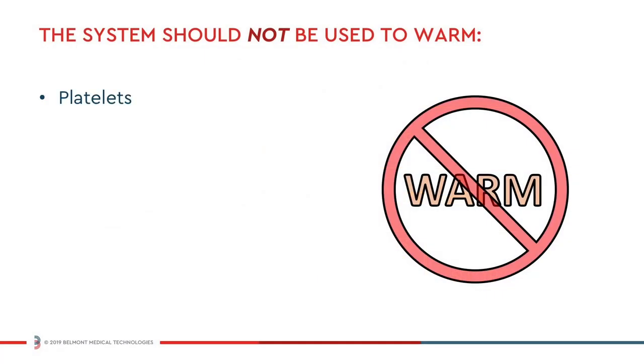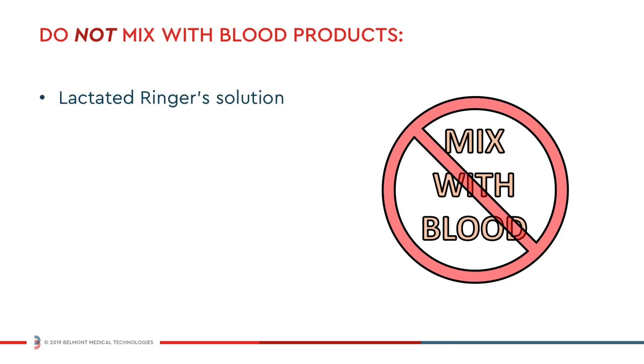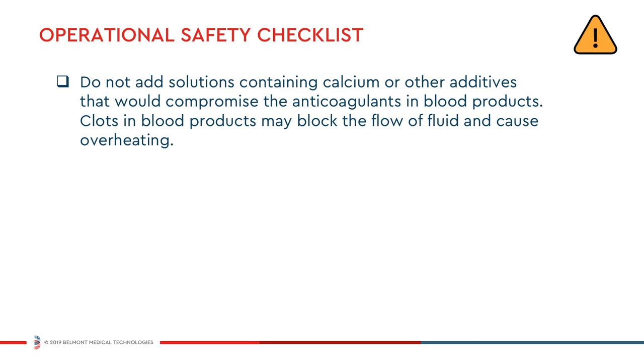The system should not be used to warm platelets, cryoprecipitates, or granulocyte suspensions. Lactated ringer solution, dextrose in water, and hypotonic sodium chloride solutions should not be added to blood components. Do not add solutions containing calcium or other additives that would compromise the anticoagulants in blood. Clots in the blood products may block the flow of fluid and cause overheating.